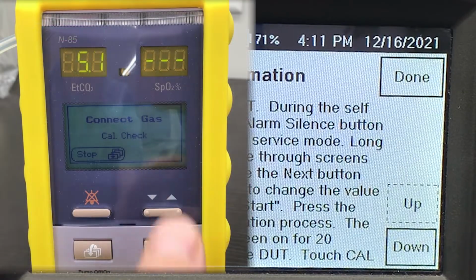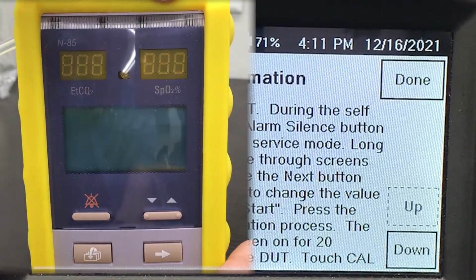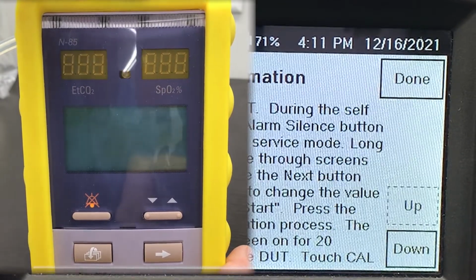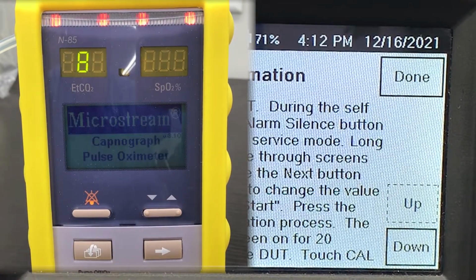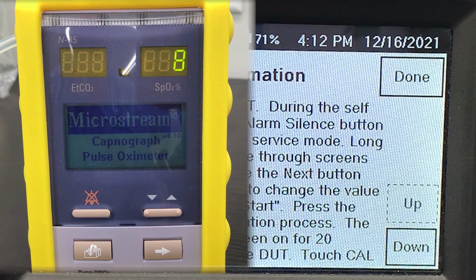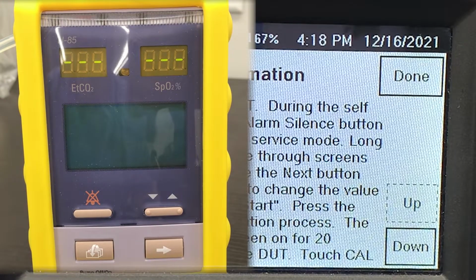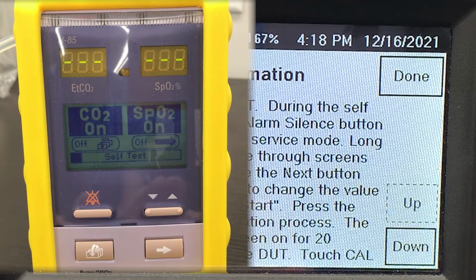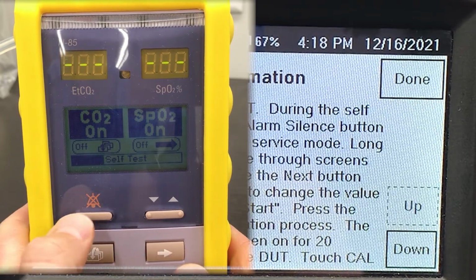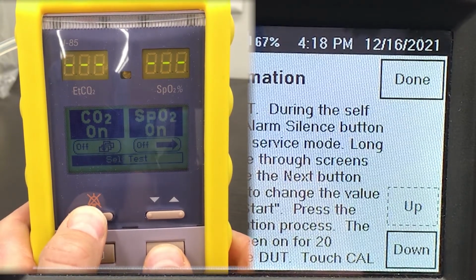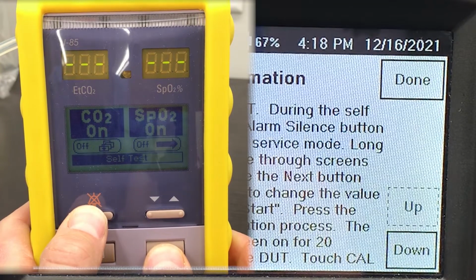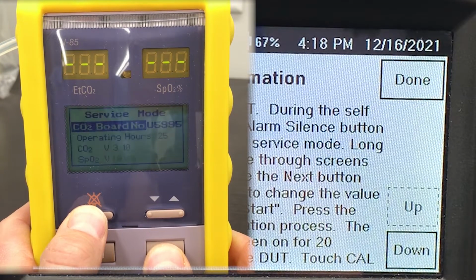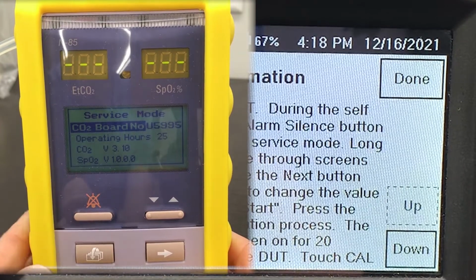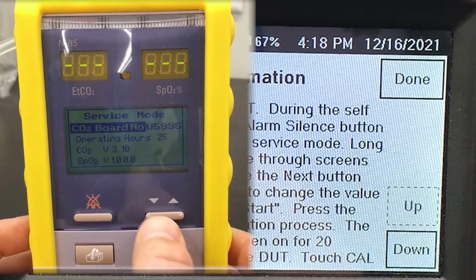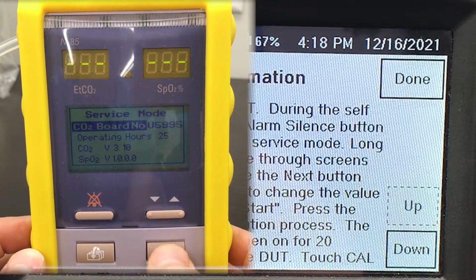Okay, so the way we calibrate the monitor is by turning it off, then we power it back on, and we wait until the monitor is in self-test. While self-test mode is running, we hold down the alarm silence and the next button. We just keep holding it down until it's done with the self-test. It comes into the service mode. This is where you can see the operating hours. You can see it's had 25 operating hours.